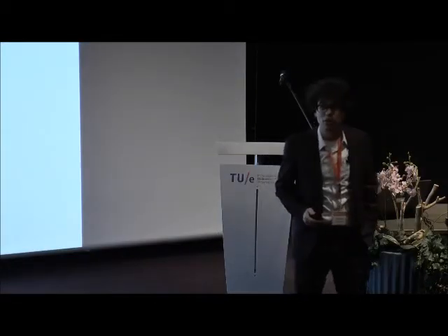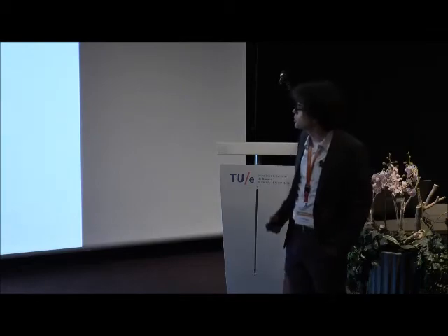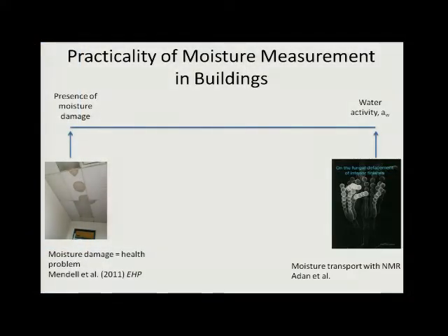And by the way, it might not be microbiological, it might be chemical for all we know, but moisture is a problem. But if we go to the extreme other end of the scale, there's some really compelling research that's been done for many years here in Eindhoven by Olaf Adan, where you look at a parameter called water activity. And he uses nuclear magnetic resonance imaging to look in very great detail at moisture and moisture transport and its association with fungal growth in building materials. Now, the problem with that is that it's lab-based research. It's very hard to do that in situ in buildings, but I think it offers us a lot of mechanistic understanding.